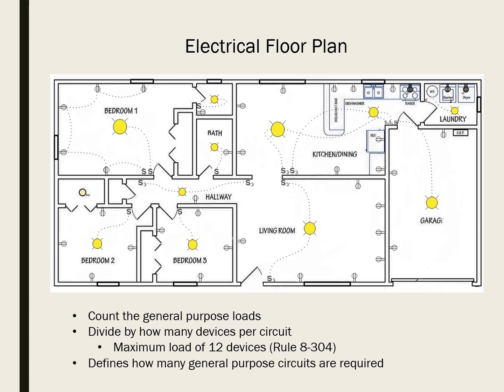You can't forget to add up all your common loads as well. We need to go through the electrical plan and add up all the outlets and lighting that are going to be considered to be general use areas. Section 26 tells us what kind of circuits need to be on their own dedicated breakers, such as microwaves and fridges and freezers, as well as how many devices that we can put on any single breaker.